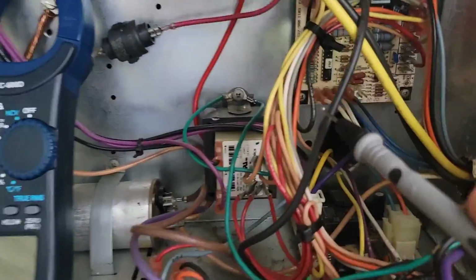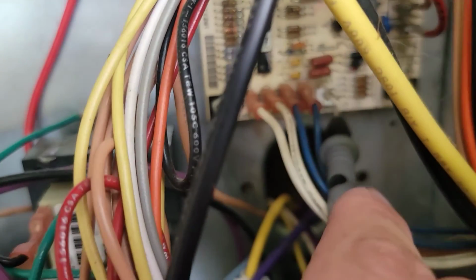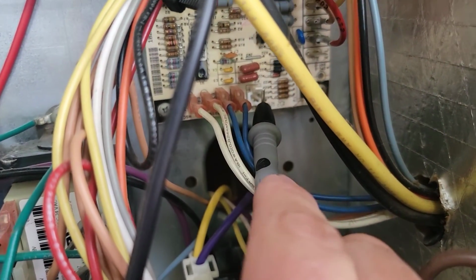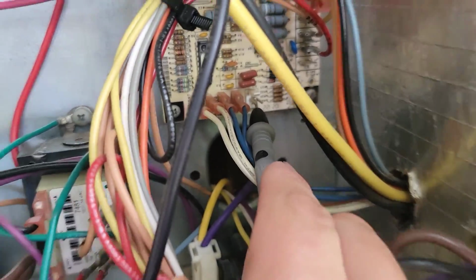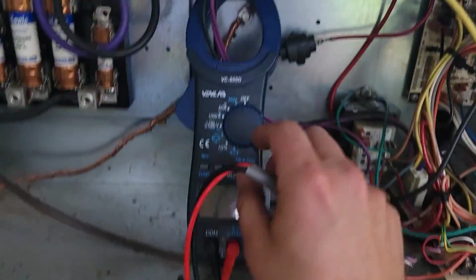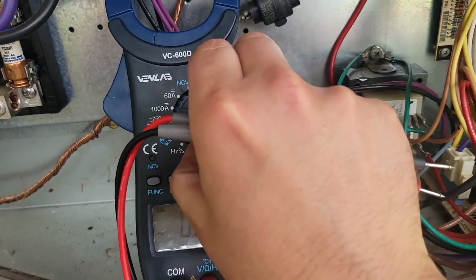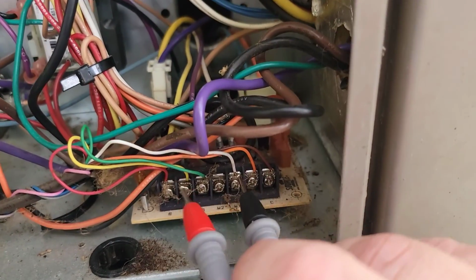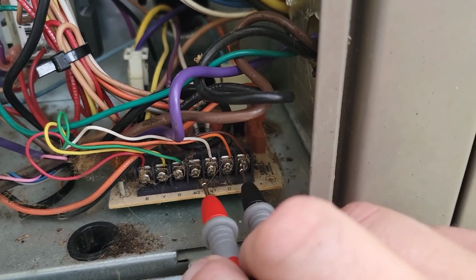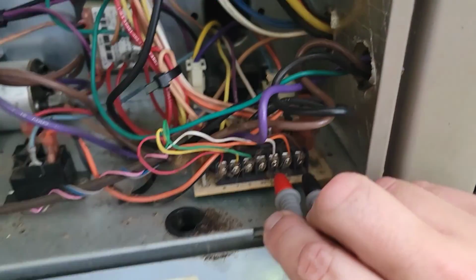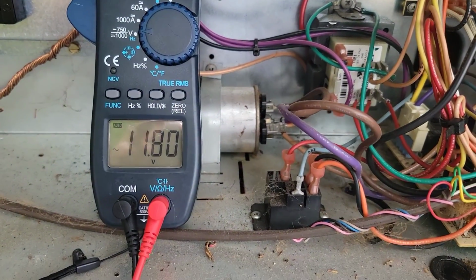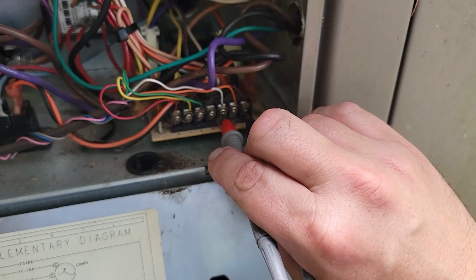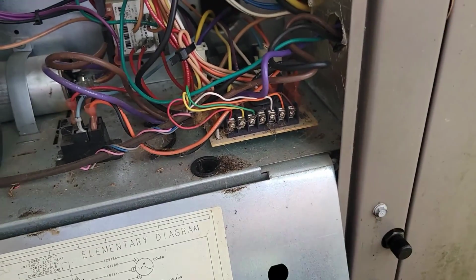You can hear the indoor blower going. It always comes on first. And you can bypass a little delay through this board by shorting across these test pins. Watch. Oops. See? Now outdoor fan came on. Take the test leads. Turn it to volts. I'm going to check from common to W1. Still got 11. Ooh, definitely not the thermostat. Glad I had an extra thermostat. So it's definitely not the thermostat.